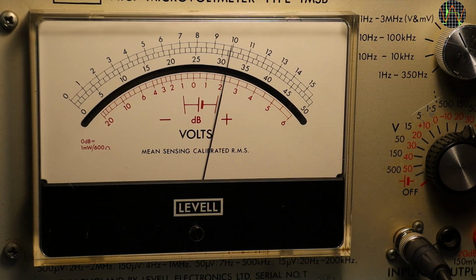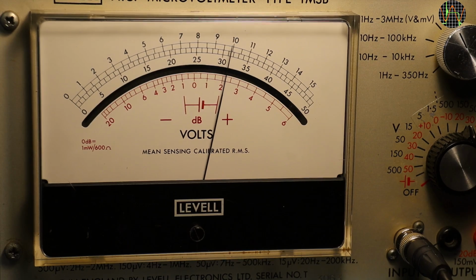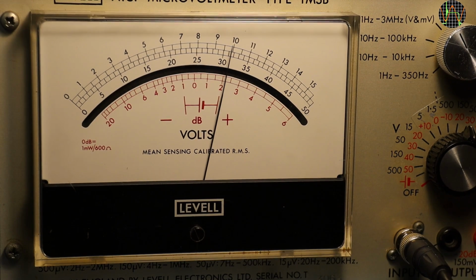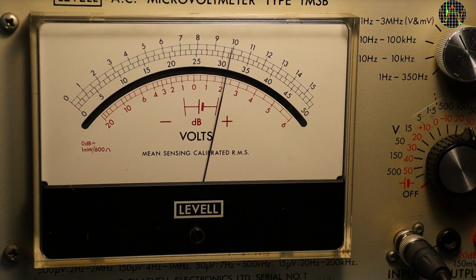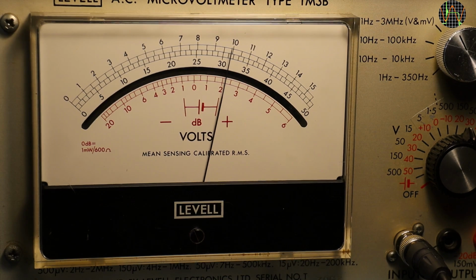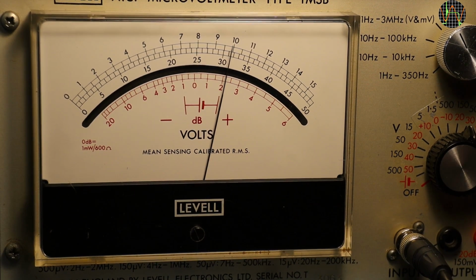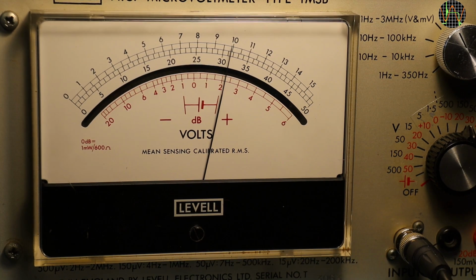Back to the TM3B. The 50 mV range reads a little low, which can be corrected by increasing the amplifier gain. Changing gain means an overall cal in all other ranges is needed, since gain affects everything else. Well, it can't be helped, so here it goes, but I'm showing this boring process a little faster as it's a repeat from the TM3A video. With a careful adjustment of the gain, the 50 mV range now reads correctly. This also fixes the ranges lower than 50 mV.